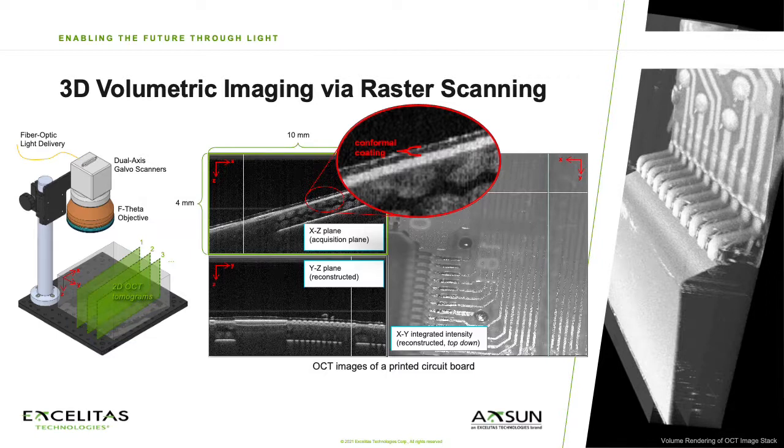By calibrating the optical scanner setup against a known reference and applying additional geometric distortion correction if necessary, high measurement accuracy on the order of tens of microns can be achieved in the XY dimension. In the Z dimension, the optical resolution is determined by the imaging laser's spectral range and is typically less than 10 microns, but can approach 1 micron for some state-of-the-art OCT systems.